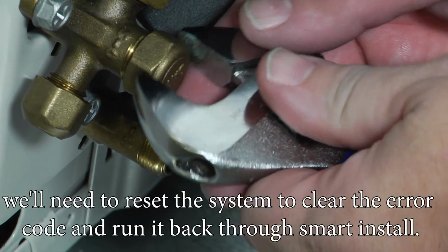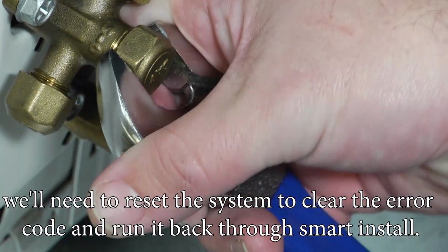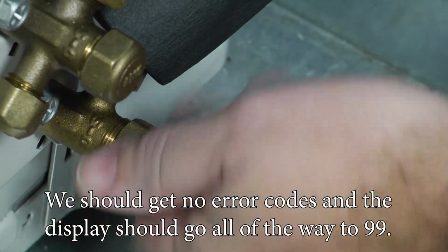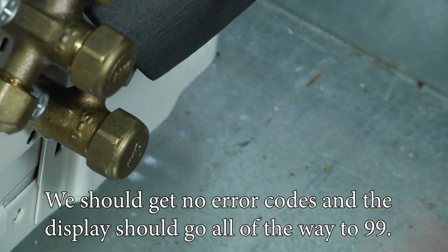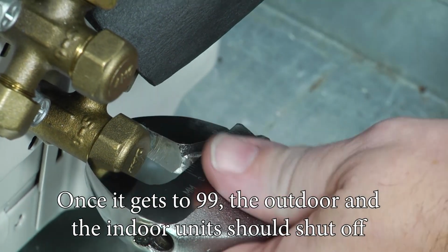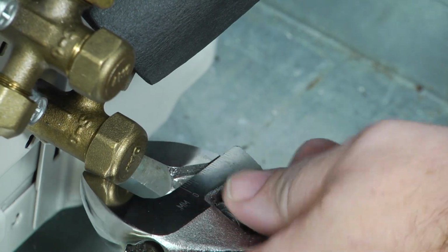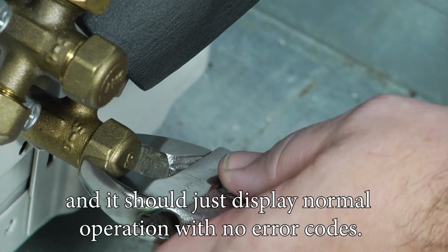Now that we've fixed the service valve and opened it completely, we'll need to reset the system to clear the error code and run it back through Smart Install. We should get no error codes and the display should go all the way to 99. Once it gets to 99, the outdoor and indoor units should shut off and it should just display normal operation with no error codes.